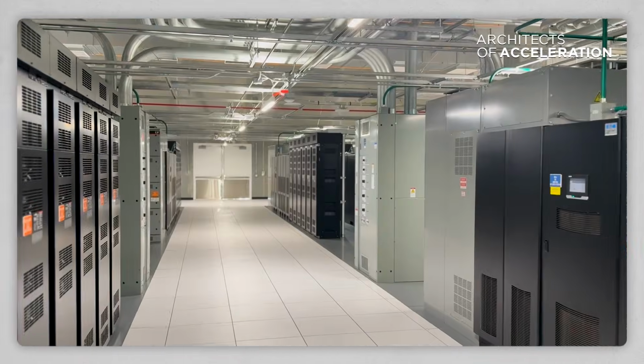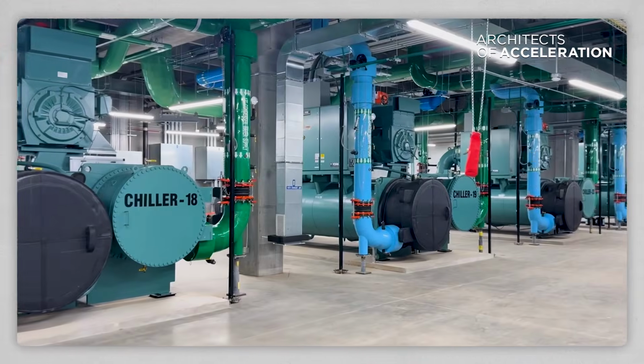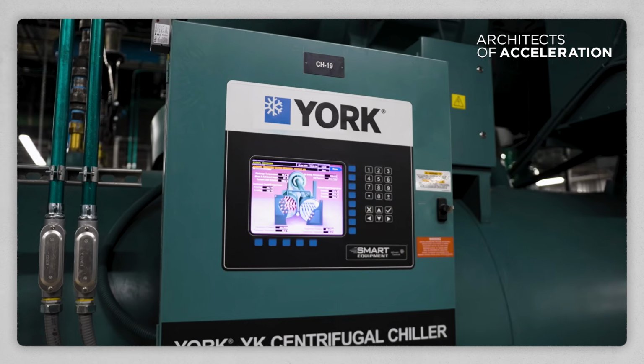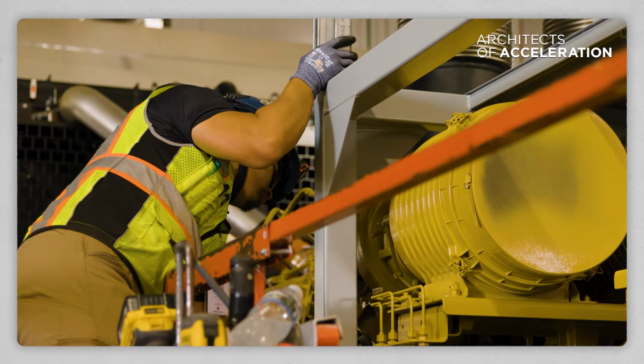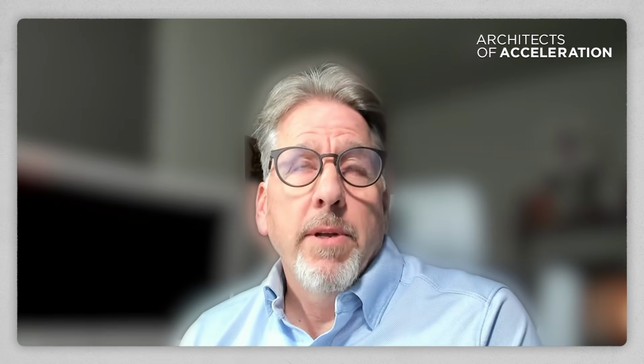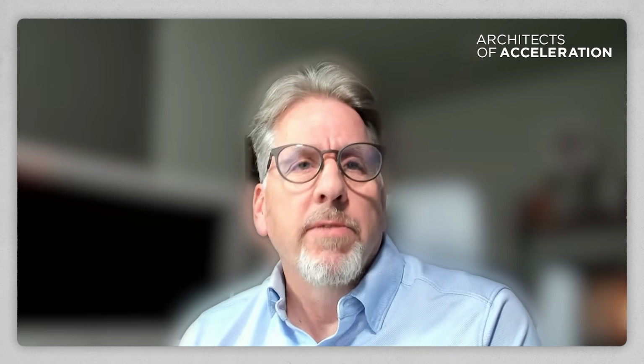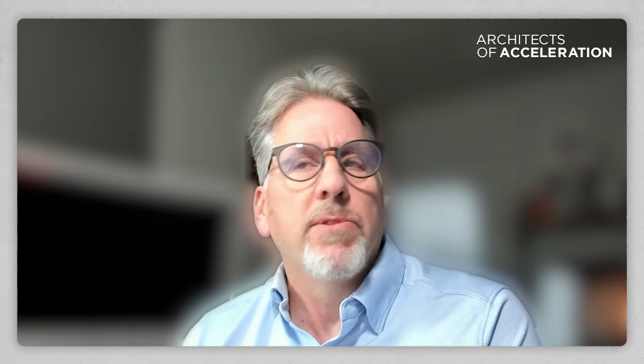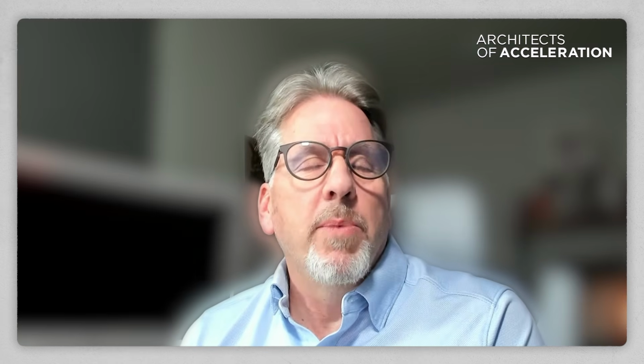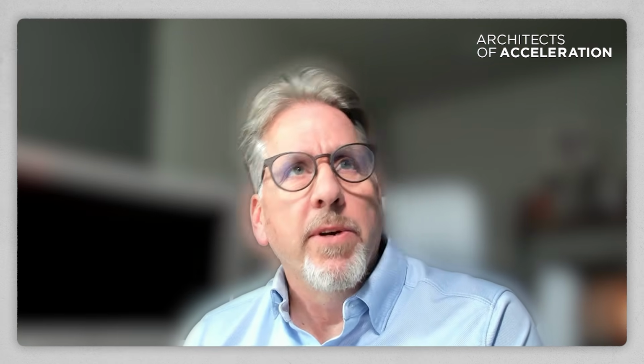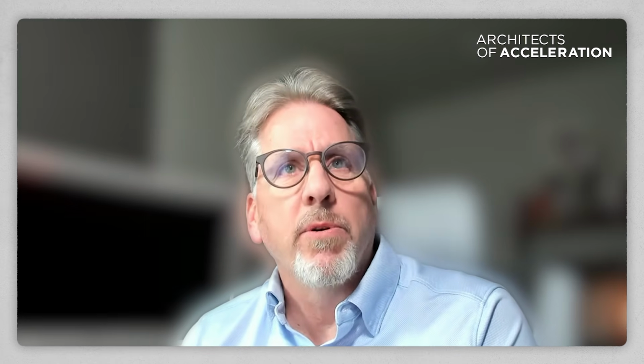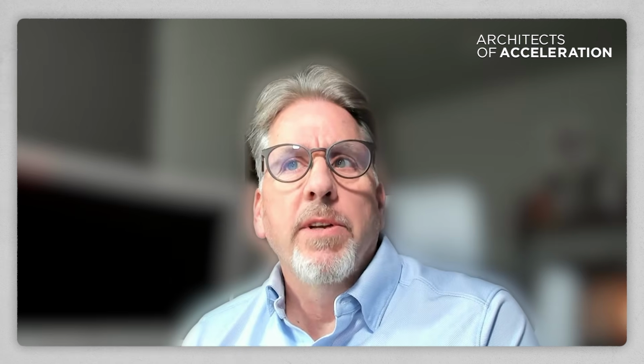For us, commissioning is a process. That's where we jump in and test our electrical, mechanical, and building management systems, and their associated equipment, to ensure they operate per our requirements and design standards. It starts probably 2 months from ready for service, and it goes through all of our systems, checking point to point to make sure all the equipment operates the way it's supposed to when we hit the set points we've programmed in. So that's how we look at our commissioning.